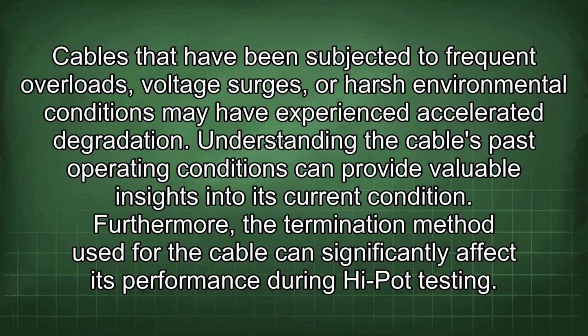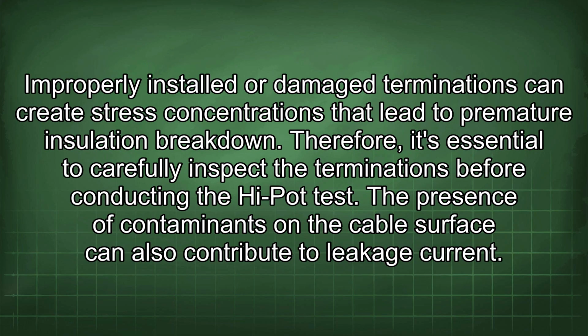Furthermore, the termination method used for the cable can significantly affect its performance during high-pot testing. Improperly installed or damaged terminations can create stress concentrations that lead to premature insulation breakdown. Therefore, it's essential to carefully inspect the terminations before conducting the high-pot test.